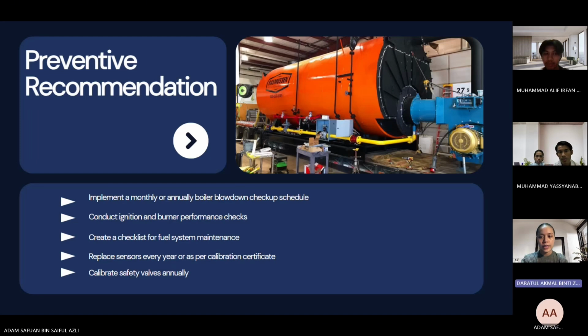For preventive recommendations, prevention is always better than cure. The first one is to implement a monthly or yearly boiler blowdown schedule to reduce scale build-up. Second, conduct regular ignition and burner performance checks to ensure combustion efficiency. The third one is to schedule periodic fuel system maintenance, especially for nozzles and filters. Then, calibrate sensors annually or according to the manufacturer's certificate. And finally, check the safety valve annually to prevent overpressure scenarios.